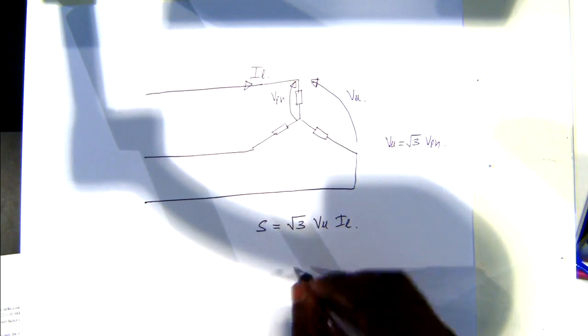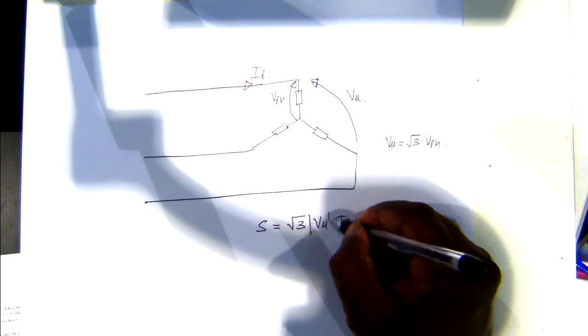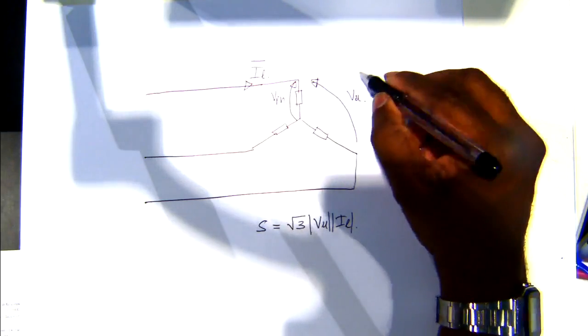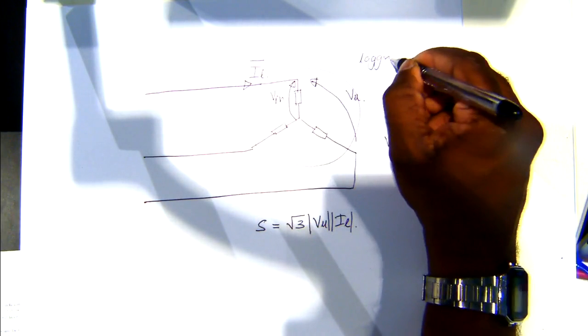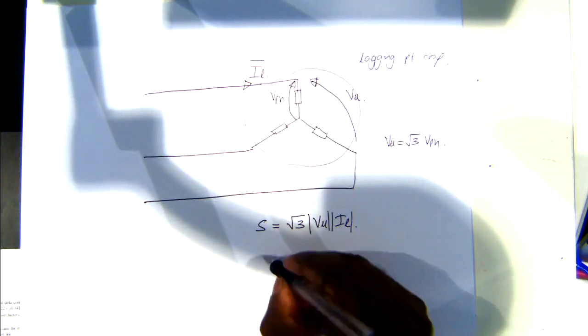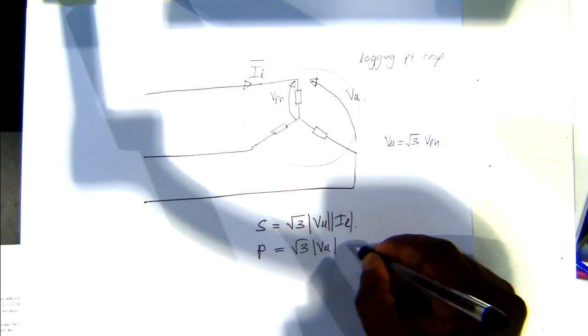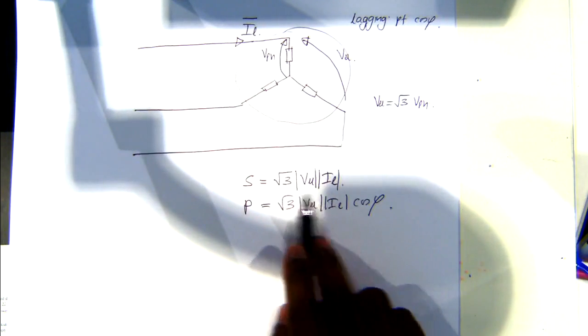If you have a certain line current, you can write the apparent power for this whole thing. S will be root three times the line-to-line voltage times I_line — that's the apparent power, and this is just the magnitudes. Then if you know the power factor — say a lagging power factor, cos phi — then your real power will be root three times V_line-to-line times I_line times cos phi. That's apparent power multiplied by power factor.